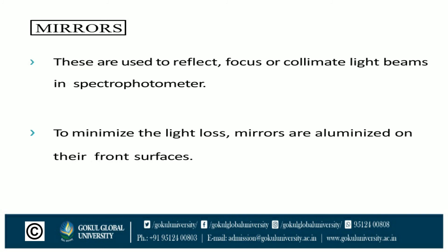Now discussing mirrors: these are used to reflect, focus, or collimate light beams in a spectrophotometer. To minimize light loss, mirrors are aluminized on their front surfaces.